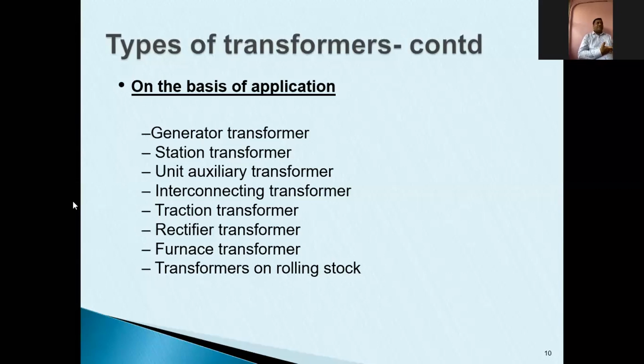When I'm talking about the station transformer, its role, as the name suggests, is very simple. It is catering to the load in that station, whether it is a generating station or a substation. So the role of the station transformer is to manage the load inside the station. There will be lighting load and auxiliary loads. When it is a generating station, you will find different plants, whether it is a coal handling plant or a boiler plant, and there will be certain loads. To handle all this load, there will be a station transformer.